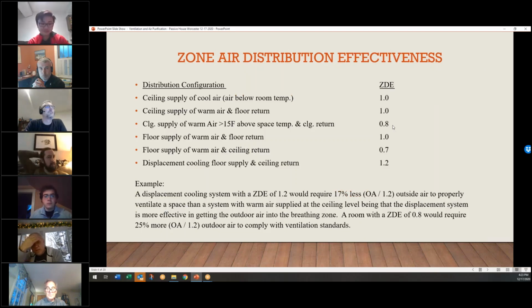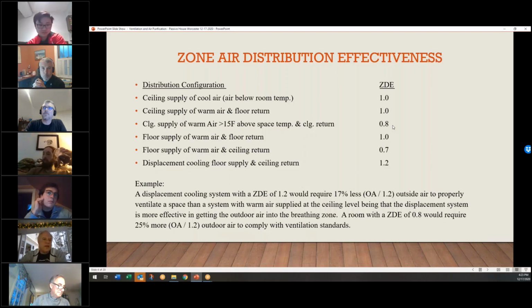Okay, so this is where the breathing zone becomes really important. I bring it up because it's something that can be easily overlooked. A lot of load calcs or ventilation programs, if you just type in a basic single zone unit, will default to a zone effectiveness of 1.0. But that might not be the case. For example, if you have a packaged rooftop unit and the supply air coming out of that unit is 15 degrees higher than space temp, which it probably would be if you're trying to hit 70 degrees, if the air goes over 85 and you have ceiling diffusers and ceiling returns, now you have to correct your outside air. You basically have to bring in 25% more outside air than what the table told you to do to meet the code. So that's something that can be easily forgotten.